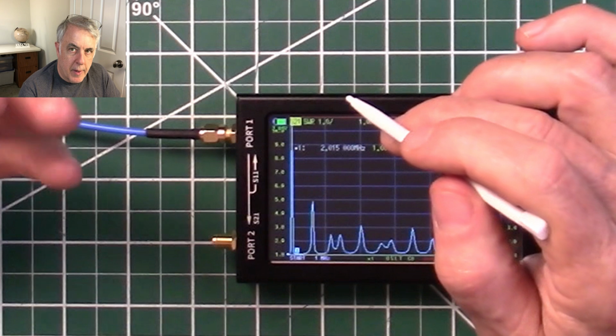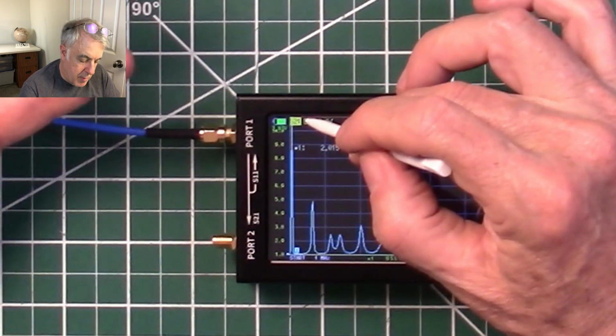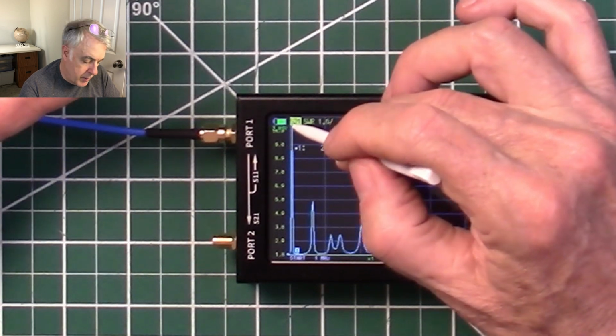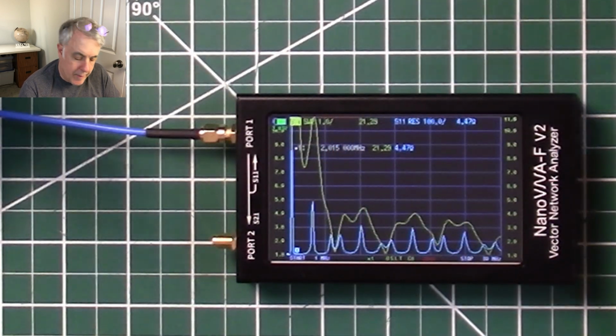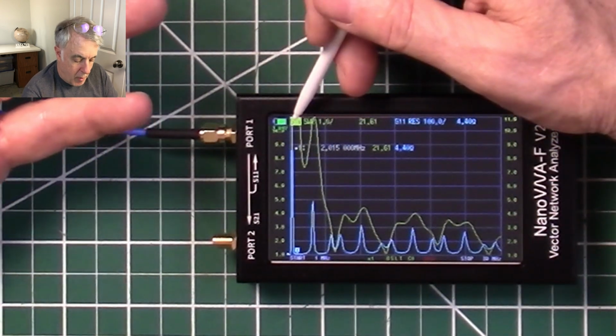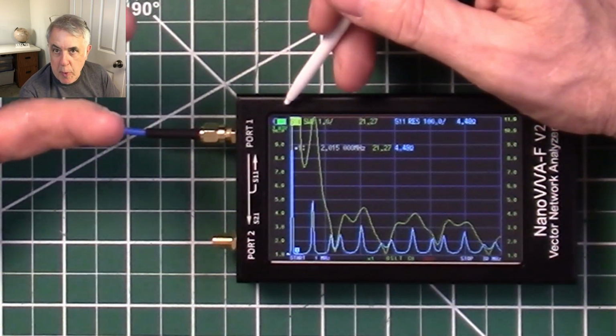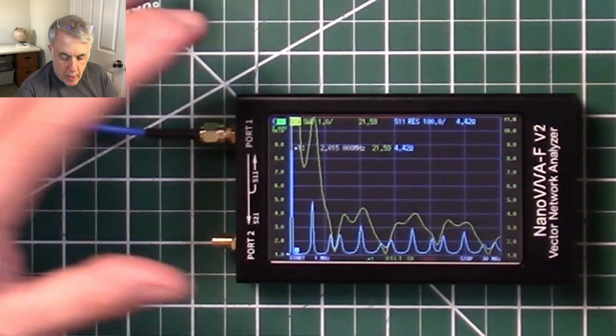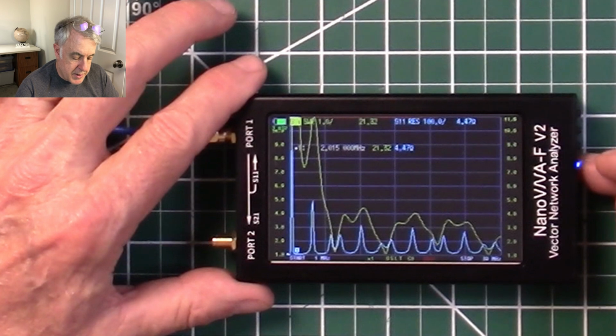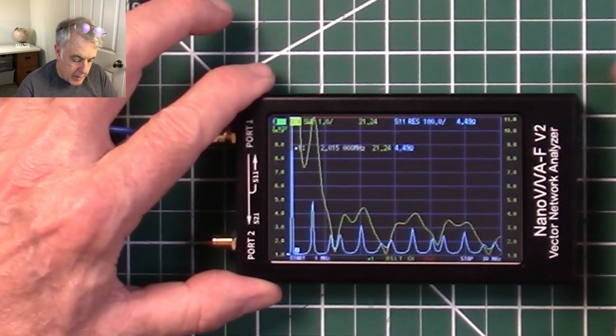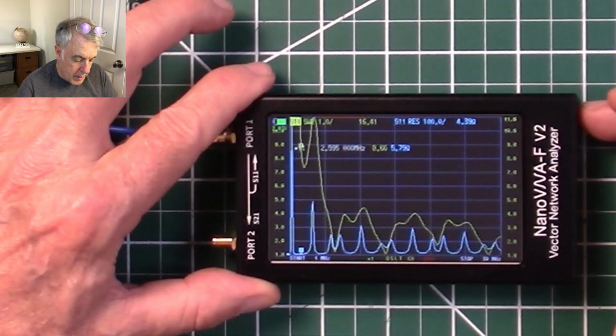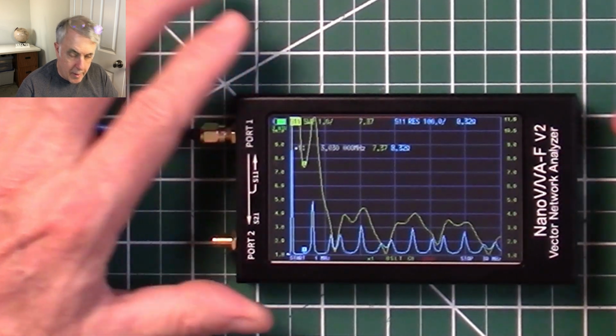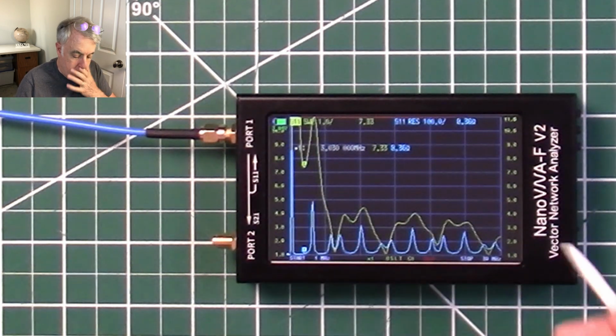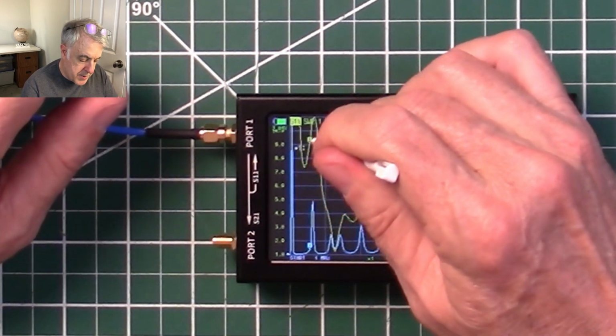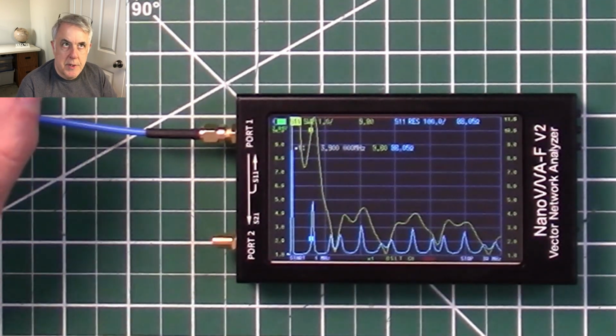It's good if the marker's not there and you want to change it, but if your marker's there and all you want to do is select the marker, you could inadvertently change your input. So I click on it again. So what do you do when the marker is being superimposed by something else or near another element? You go to your buttons for navigation. So if I want to go up in frequency, I click the top button, and there it comes down like that. And now it's here. Let's click it and drag it. I'm going to put it up there so you can see where it is.